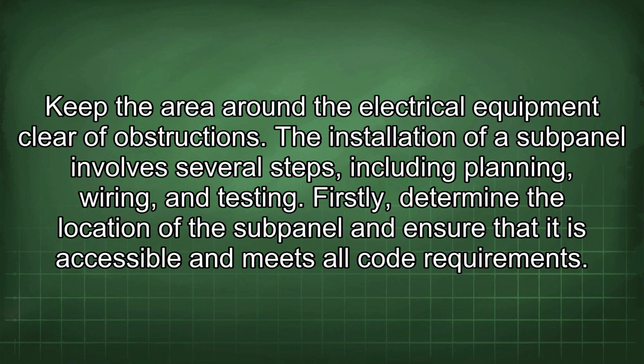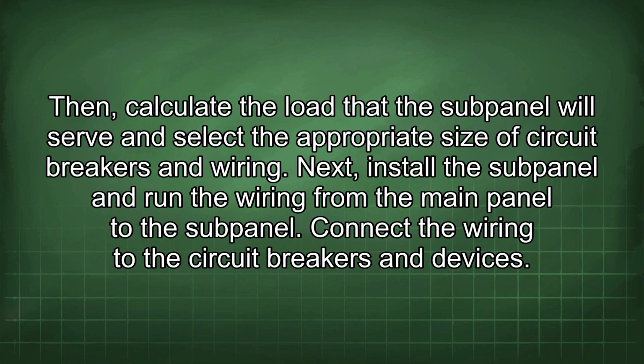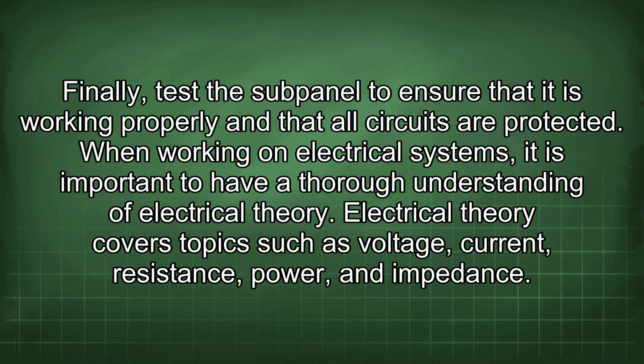The installation of a subpanel involves several steps, including planning, wiring, and testing. Firstly, determine the location of the subpanel and ensure that it is accessible and meets all code requirements. Then, calculate the load that the subpanel will serve and select the appropriate size of circuit breakers and wiring. Next, install the subpanel and run the wiring from the main panel to the subpanel. Connect the wiring to the circuit breakers and devices. Finally, test the subpanel to ensure that it is working properly and that all circuits are protected.